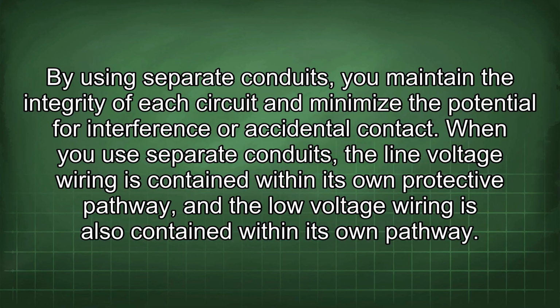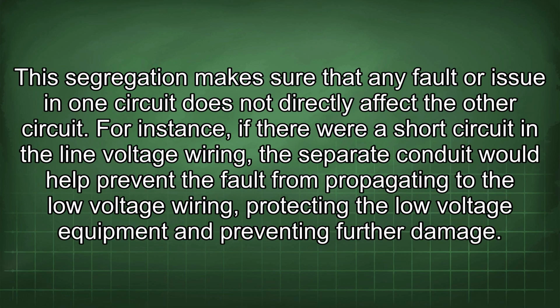When you use separate conduits, the line voltage wiring is contained within its own protective pathway, and the low voltage wiring is also contained within its own pathway. This segregation makes sure that any fault or issue in one circuit does not directly affect the other circuit. For instance, if there were a short circuit in the line voltage wiring, the separate conduit would help prevent the fault from propagating to the low voltage wiring, protecting the low voltage equipment and preventing further damage.